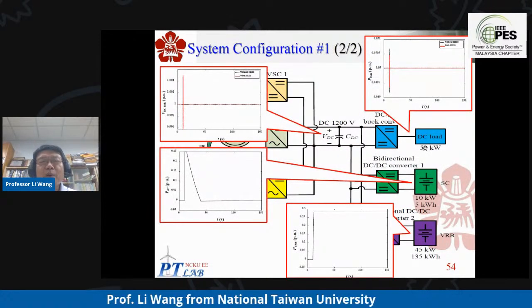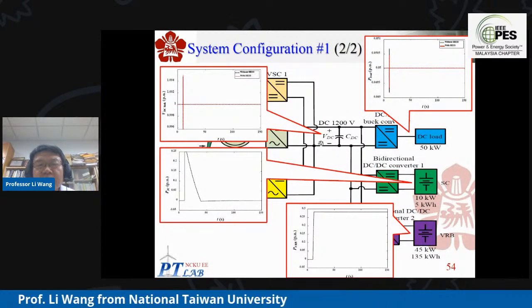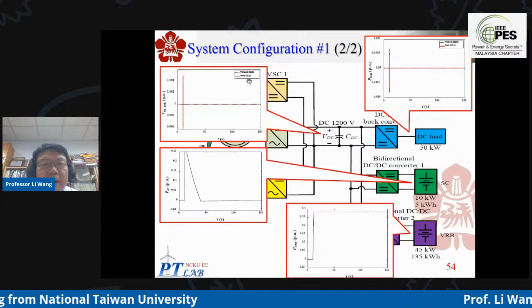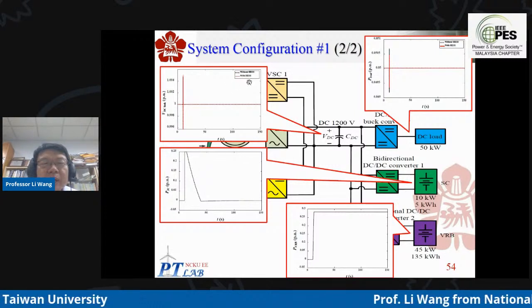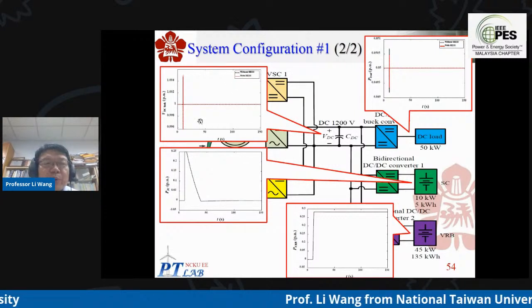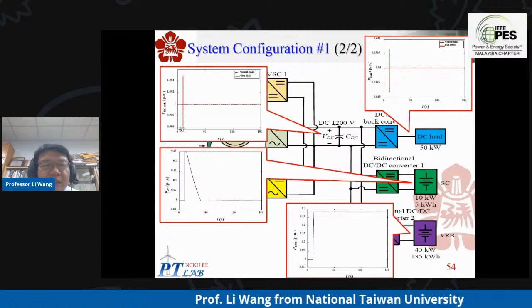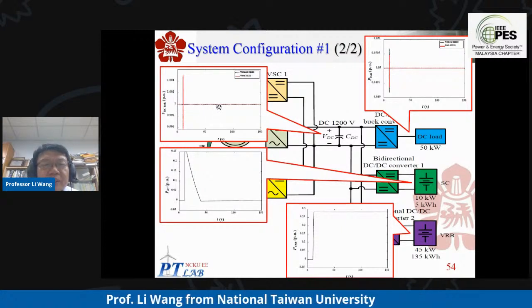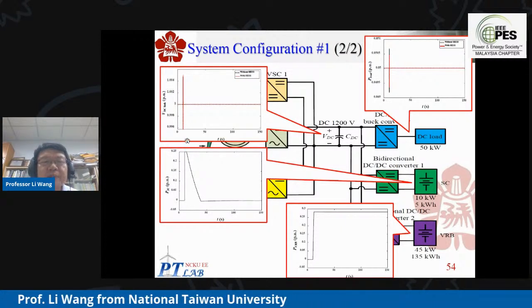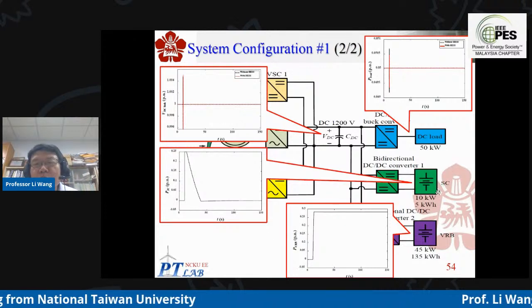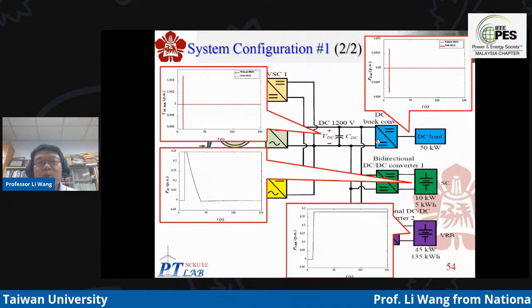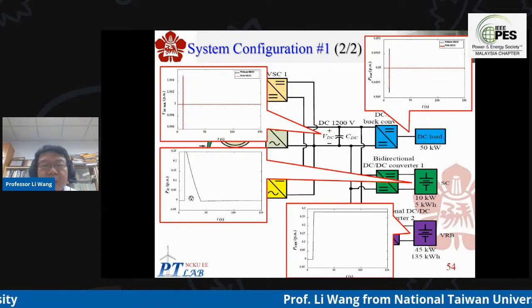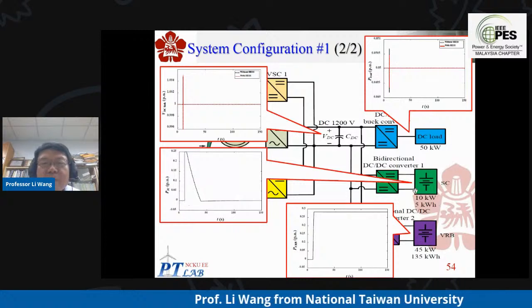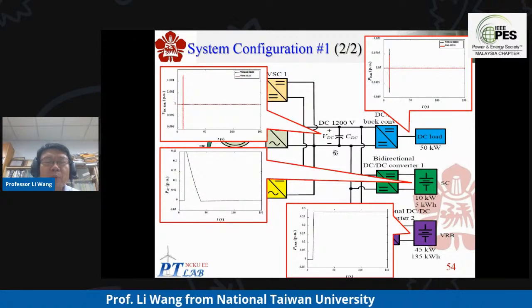When the sudden trip of the wind farm happens, what about the DC link? Here's a comparison with and without the hybrid energy system. With the hybrid system, the value stays constant; without it, large variation happens. At the supercapacitor, when the wind farm suddenly trips, its output power goes positive to compensate for the loss of power from the wind farm.